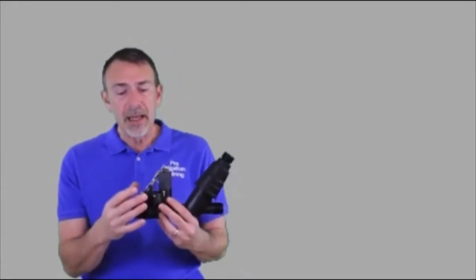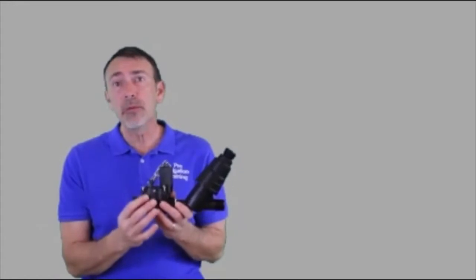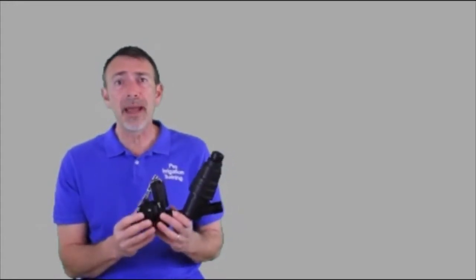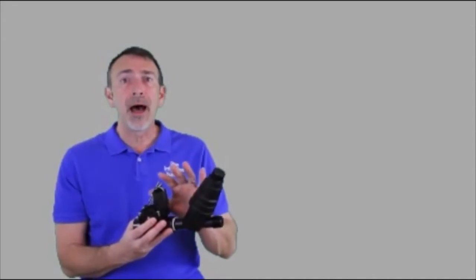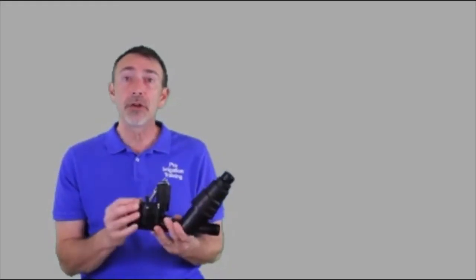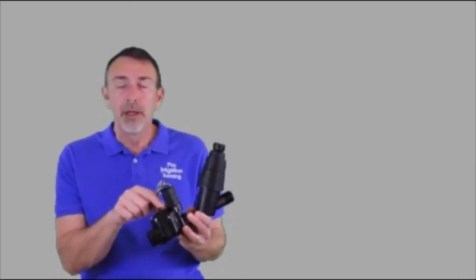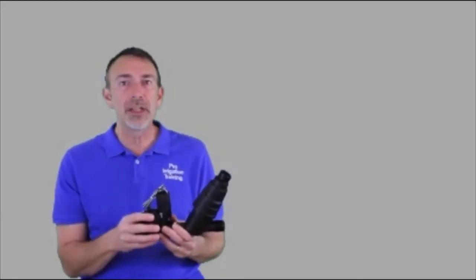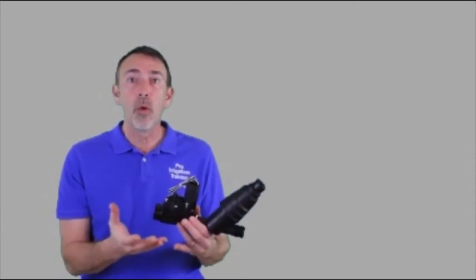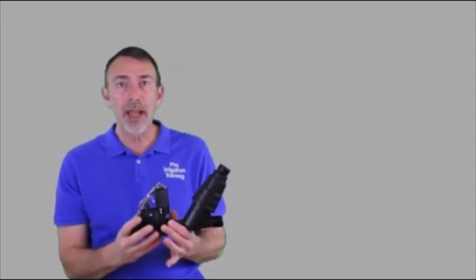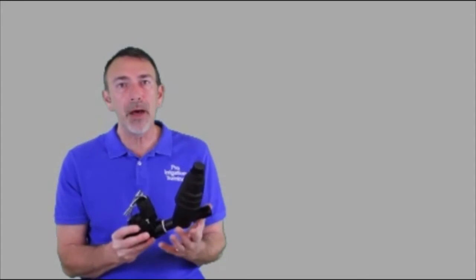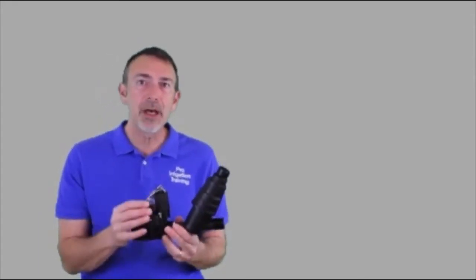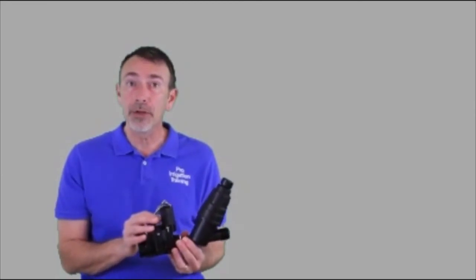And the reason is that some of these regular valves, when you get down into very low flows, the valves will start chattering or maybe they won't even open up at all. But almost all the manufacturers make a low flow version and then sometimes they'll put those into kits. My only point is don't assume that you're buying a drip zone control kit that it's low flow. Check the specifications and usually there's a marking of some kind. On Rainbird, you'll see a yellow or orange sticker right here on the top that indicates that it's low flow. And usually when you're getting variations of this product, they also make a version of this product to be used with dirty water or reclaimed water. And those have purple components on it. So if you're getting beyond the regular normal residential valves or residential products or whatever, they'll usually be marked in some way. But just make sure that you know what you're getting and then you match up the components with what you're actually using on the drip zone.